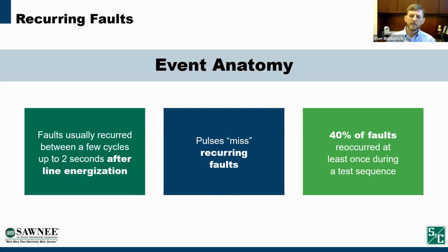So every time that it occurred during a test sequence would cause an upstream device to operate. Like I said, if it detects the fault at least once, then you just get nuisance tripping upline. But if it never detects that fault because it recurs time after time after time when you test, then it drives that upline device all the way to lockout. Next slide.